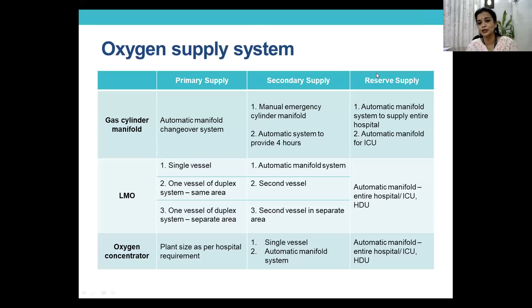Now, the third aspect is your oxygen concentrator. If you have an oxygen concentrator that can supply to your entire hospital, your backup then becomes a single vessel. You can have it as a backup. Just keep a single vessel, or you can have an automatic manifold system with auto changeover. And a reserve, again, as I mentioned, an auto manifold, a second one, or just connect your ICUs and HDUs. This is very, very, very important. Three levels of backup is critical.